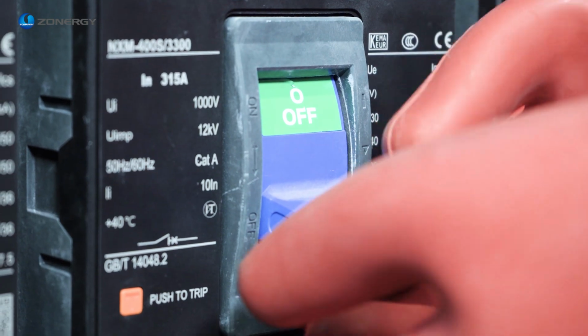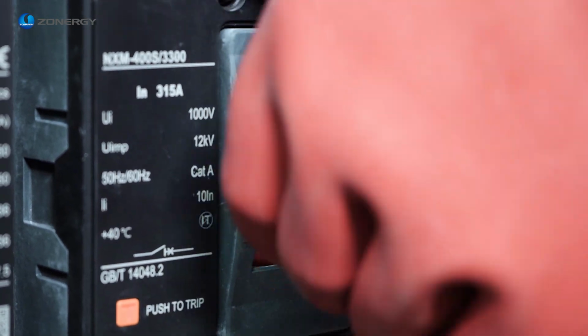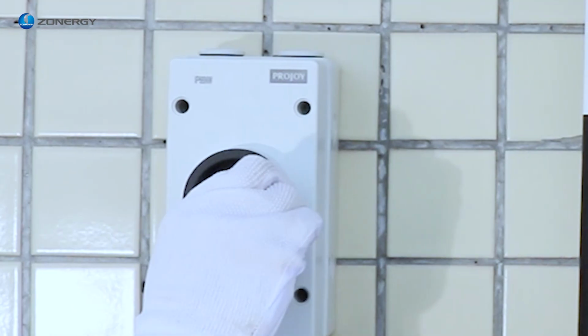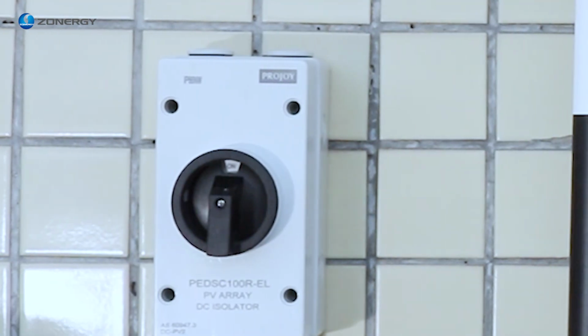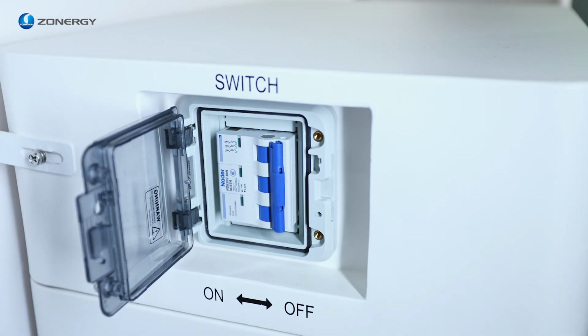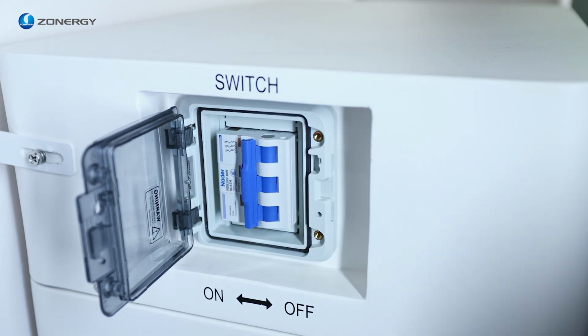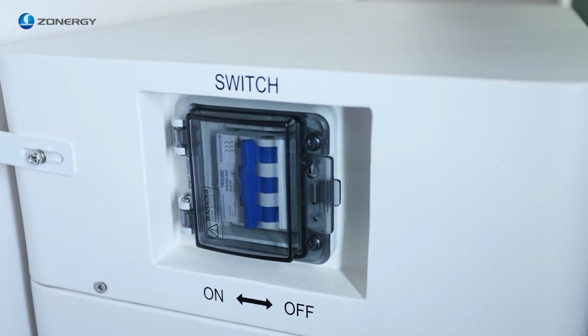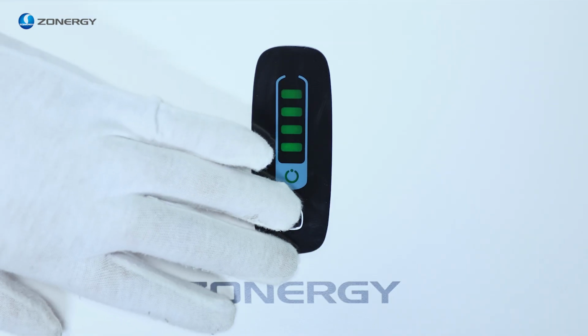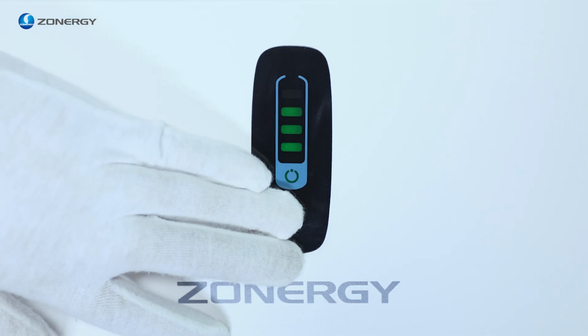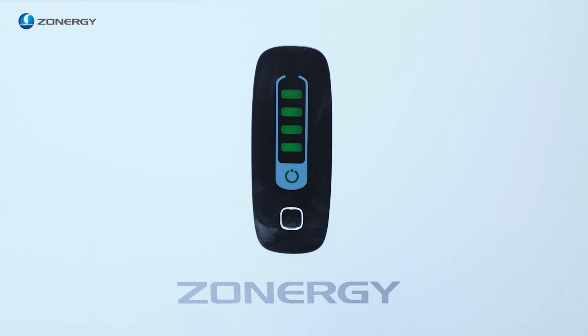Step 1. Close the inverter ON-GRID AC circuit breaker. Step 2. Close the inverter BACKUP AC circuit breaker. Step 3. Turn on the battery switch and close the energy storage circuit breaker between the inverter and the battery. Press and hold the black button on the panel of the main center control box for 5 seconds. If you hear a click sound, the battery pack relay is successfully closed.